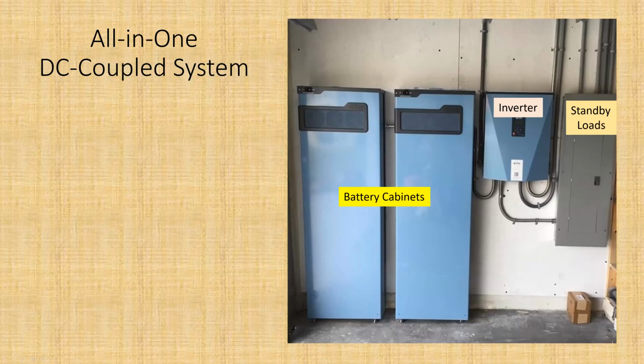Here's an all-in-one DC coupled system. Here's what it looks like. There's the inverter, standby load panel, and a couple of battery cabinets. These battery cabinets are each capable of 18 kilowatt hours of storage. So there's 36 kilowatt hours of storage here. And you notice it's pretty high voltage, because that conduit joining between the two is coupling the power from the one on the left to the one on the right. And that size conduit is certainly not going to accommodate 4-aught copper or 4-aught aluminum or 2-aught copper or whatever. And that inverter there is rated at 7,600 watts. When I first saw that, I couldn't believe it, but there are no transformers in these. So they are light and efficient and very good.